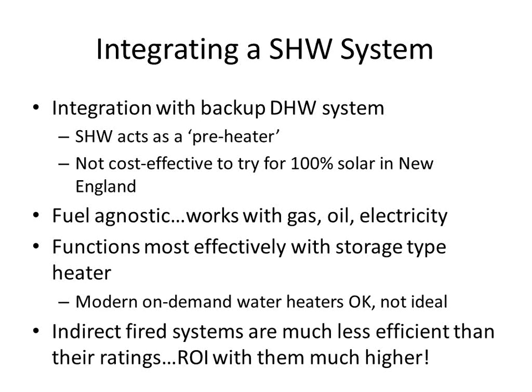In the summertime, when you have no heat load for that boiler other than your domestic hot water, that boiler is either going to shut down and have to completely reheat every time you call for heat, or you're going to have to keep that boiler core warm all the time. And what we found is indirect fired domestic hot water systems are operating at efficiencies in the summertime of well under 50%. And it took a lot of looking at data to really understand that and start getting at why that was.